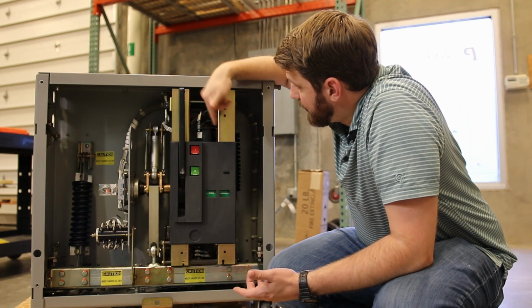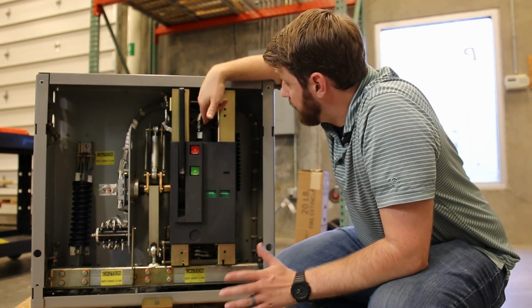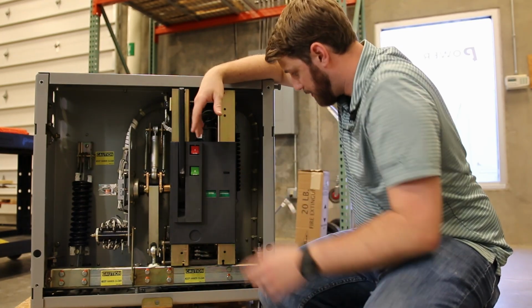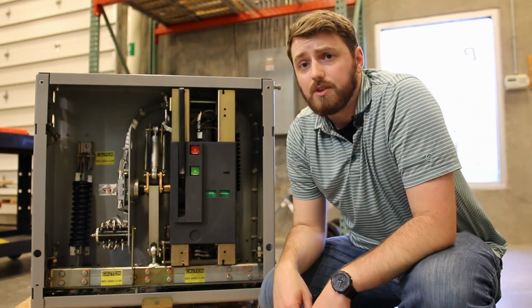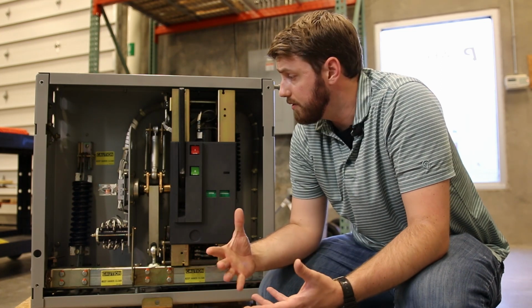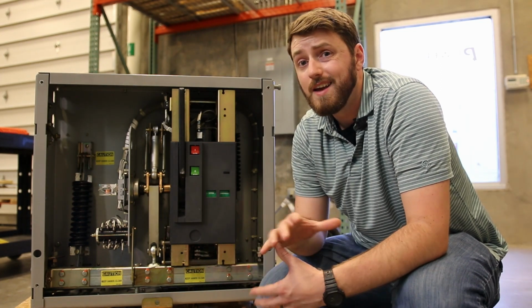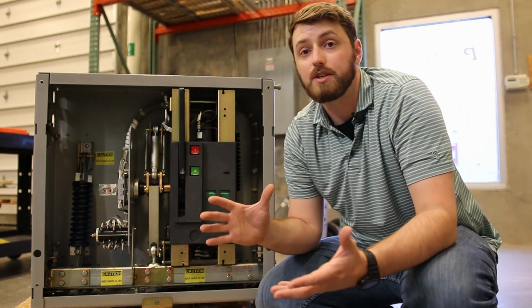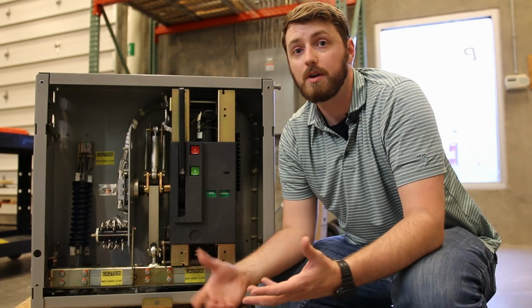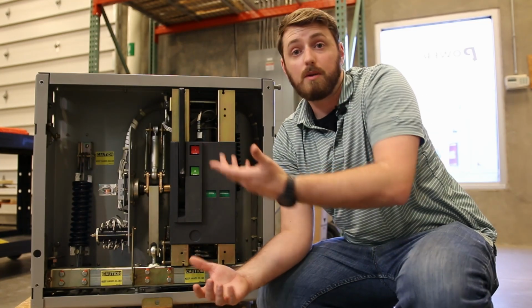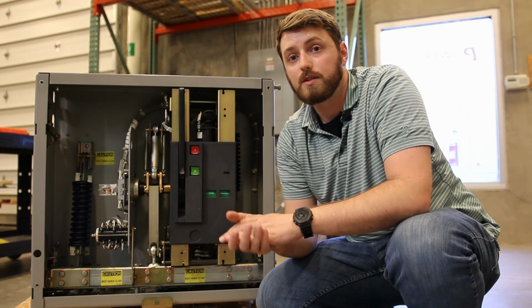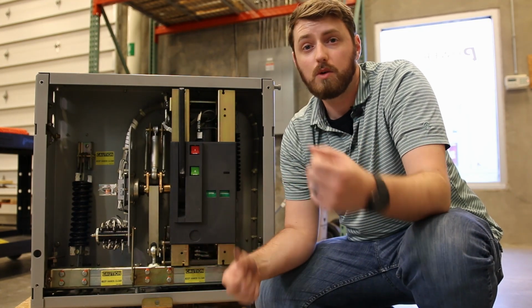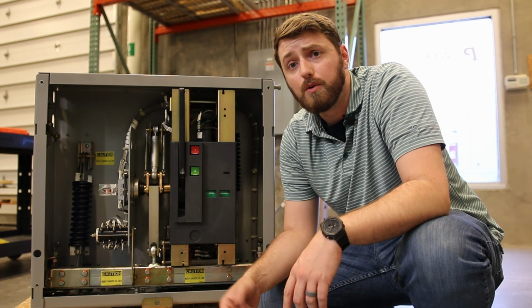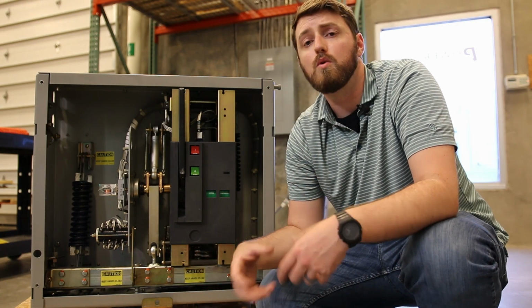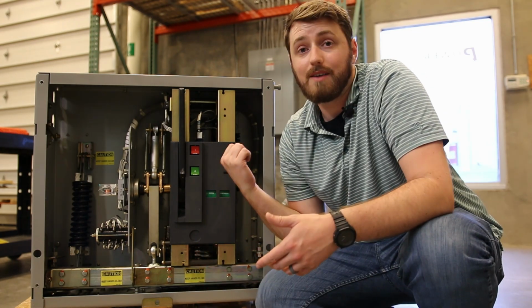But realistically, we've got a couple of coils. We've got the trip and the close coil in here somewhere. Doesn't really matter which one's which. We've got a couple more status contacts, but you'll notice, very dissimilar to all of the low voltage circuit breakers, there's no protection. There's nothing that tells it when to trip. This is how it physically trips. Voltage is applied across the coil and it physically opens or closes. But there's no control. There's no overcurrent element. This doesn't even have CTs in it.